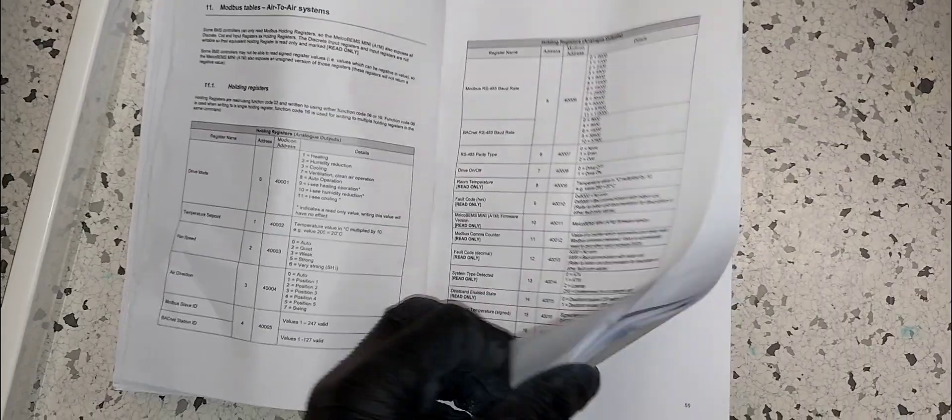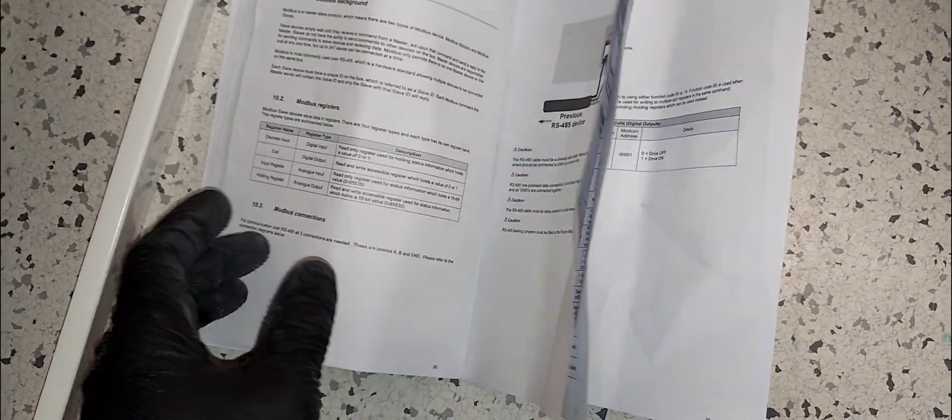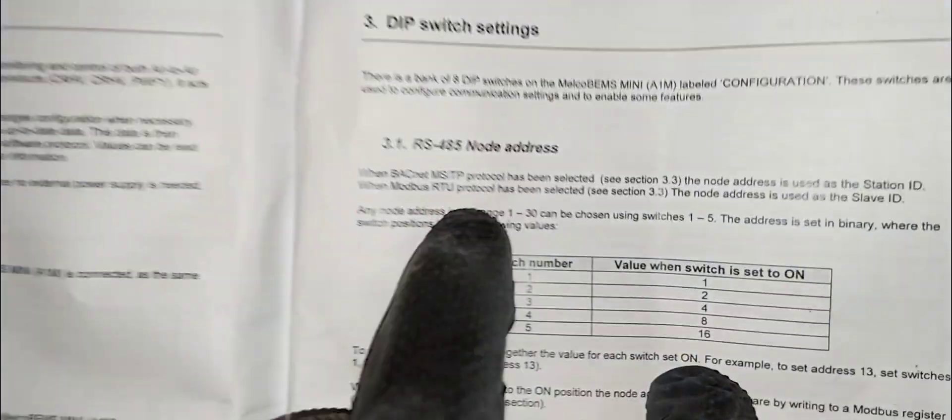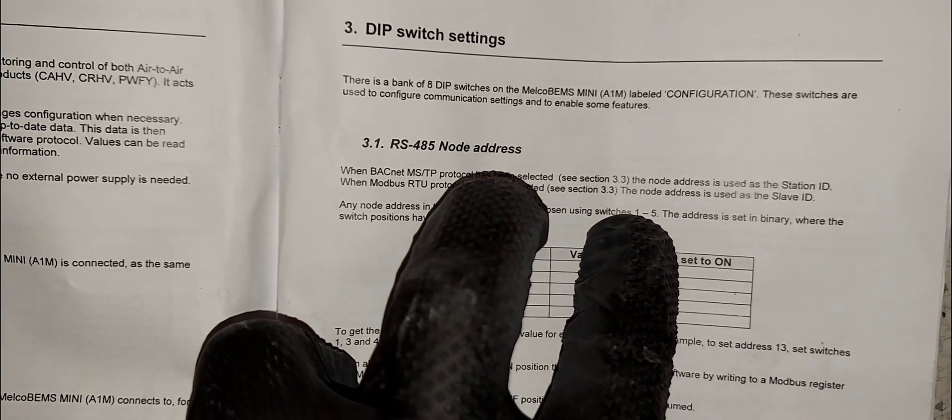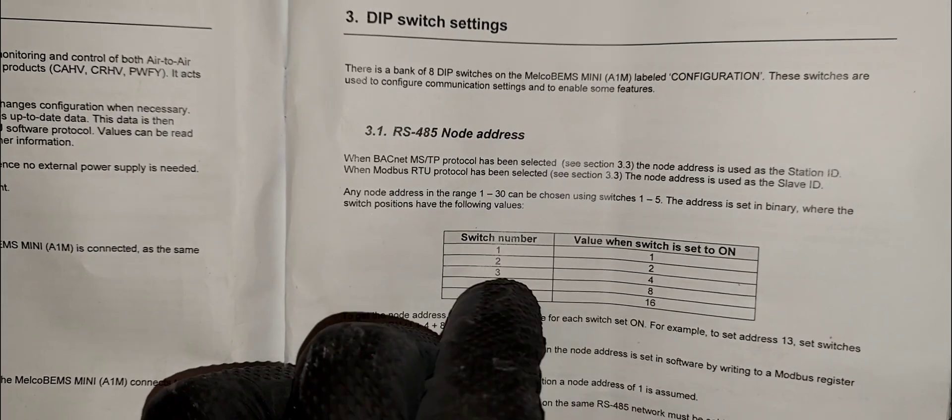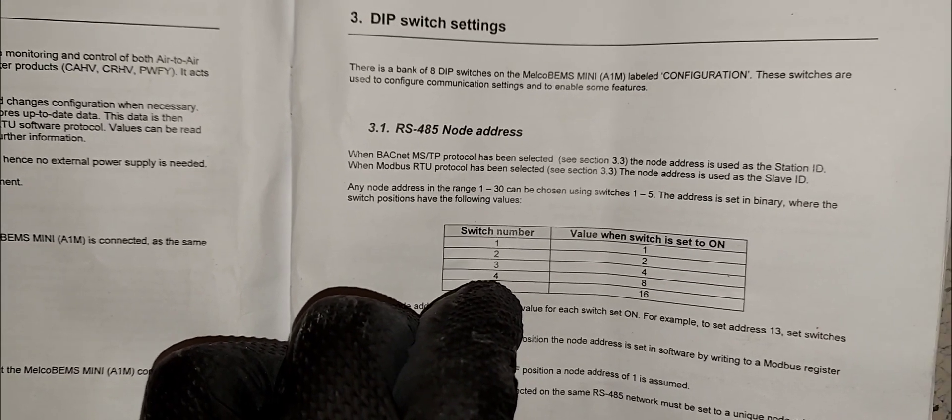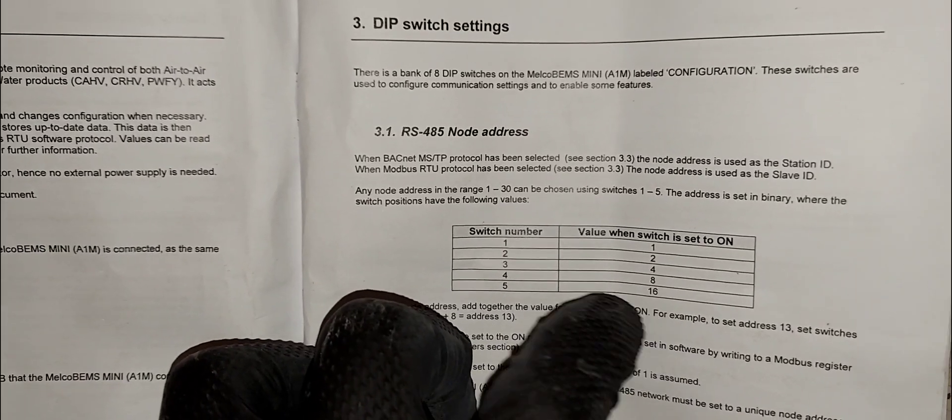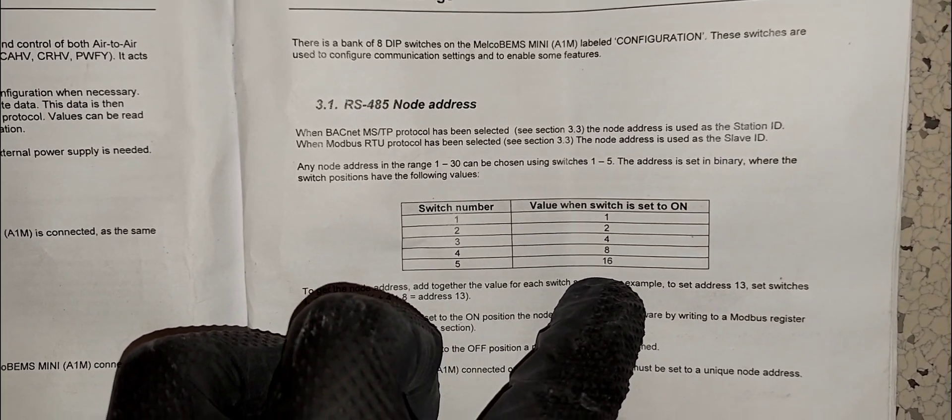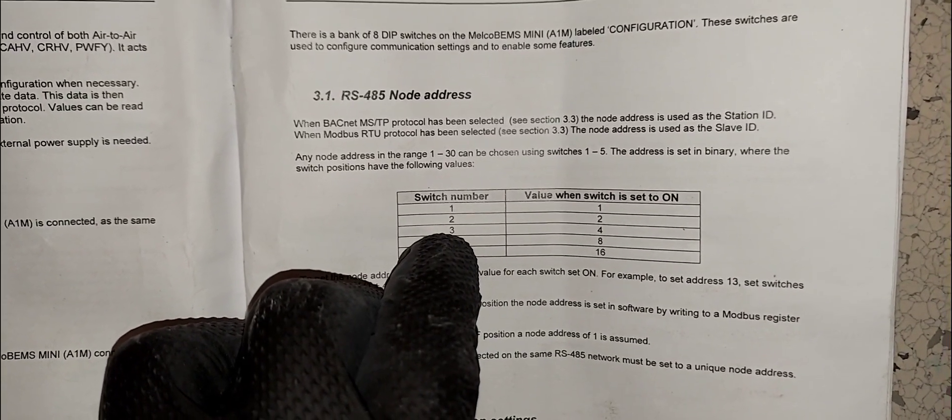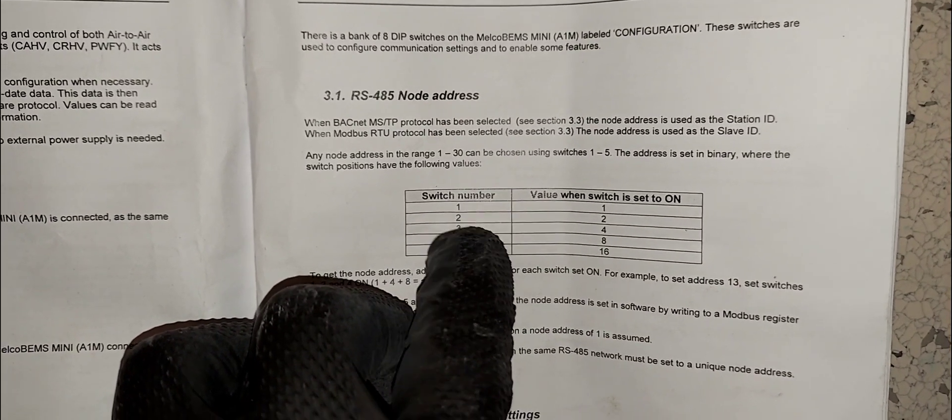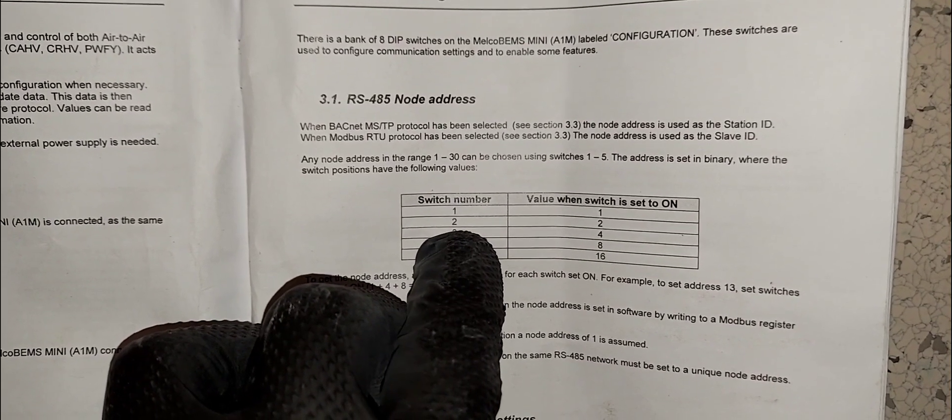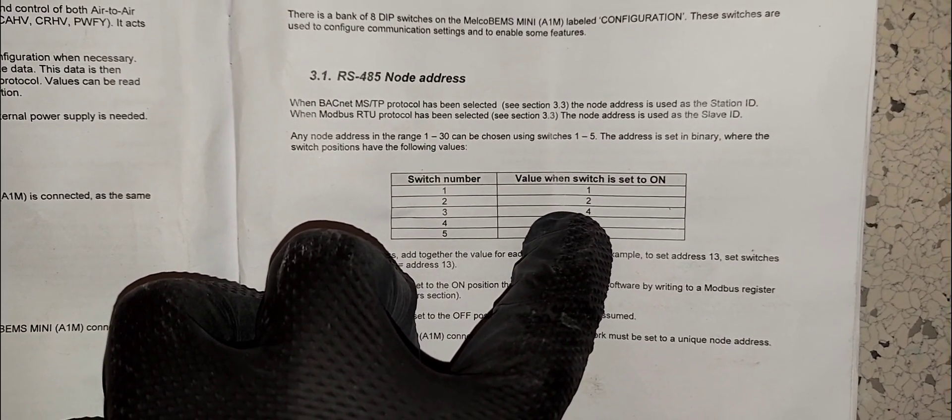What I'll be doing here today is setting the address for this node. The address ranges from 1 to 30 using a series of five switches - switches one through five. They are binary so you're going to combine your numbers. If you want address number four, you will turn switch number three on and everything else off. With switch number three on, that's address number four.